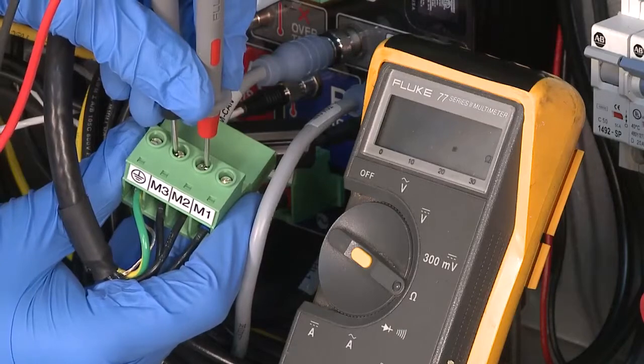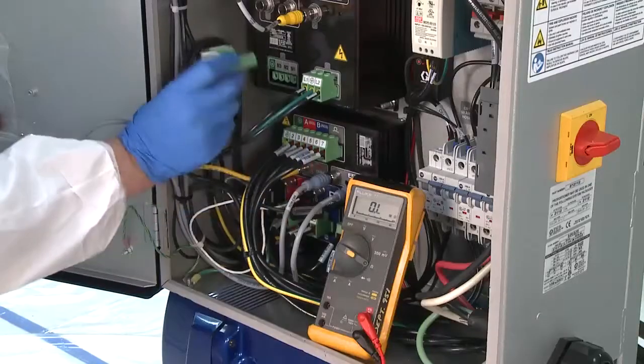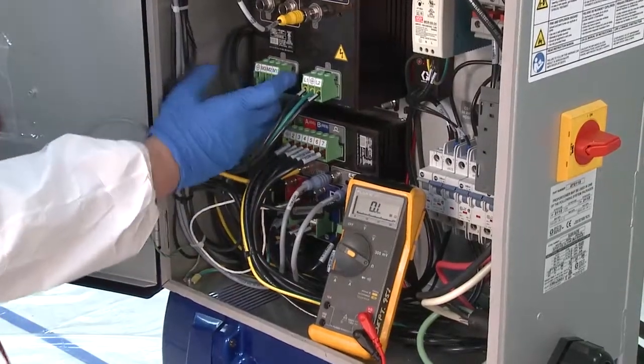If any readings are greater than 8 ohms and the previous causes discussed have been investigated, then the motor may need replacement.